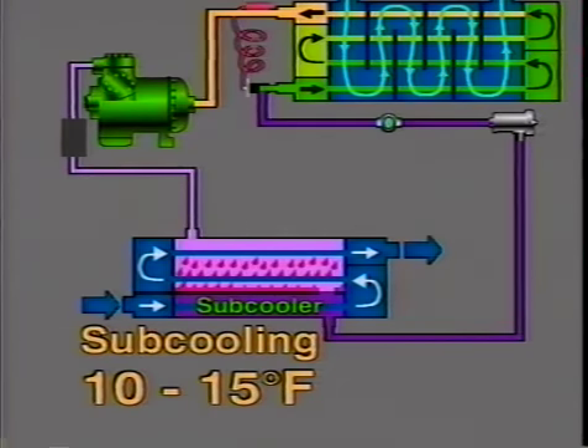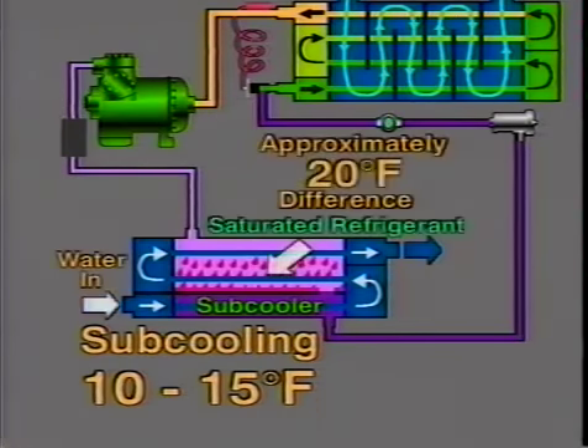This subcooling is important because it improves capacity by ensuring that the refrigerant is still 100% liquid by the time it enters the expansion valve. Any flashing of the liquid ahead of the expansion valve greatly diminishes the chiller's capacity. There should be approximately 20 degrees Fahrenheit temperature difference between the saturated condensing temperature of the refrigerant and the temperature of the entering condenser water to maintain the 10 to 15 degrees of subcooling.